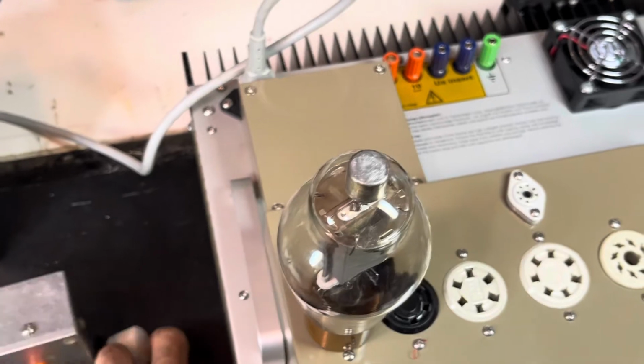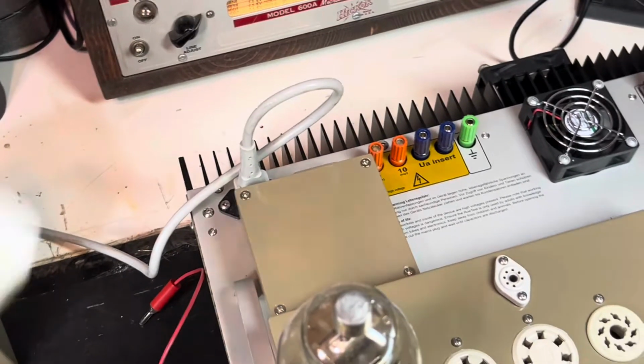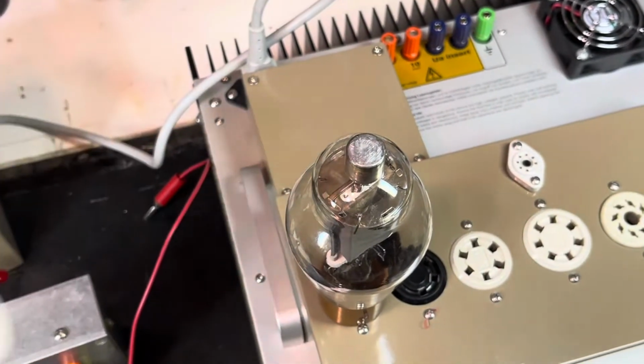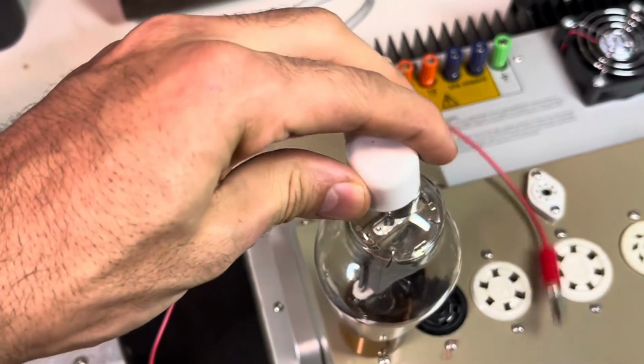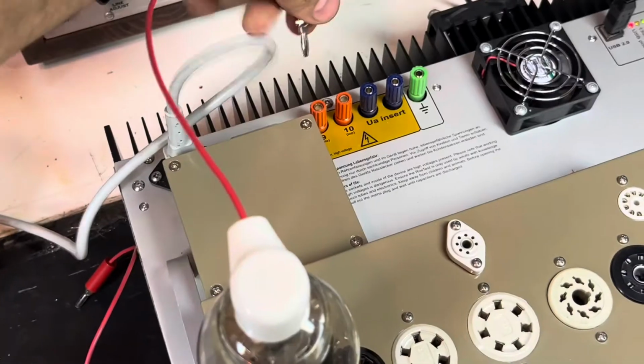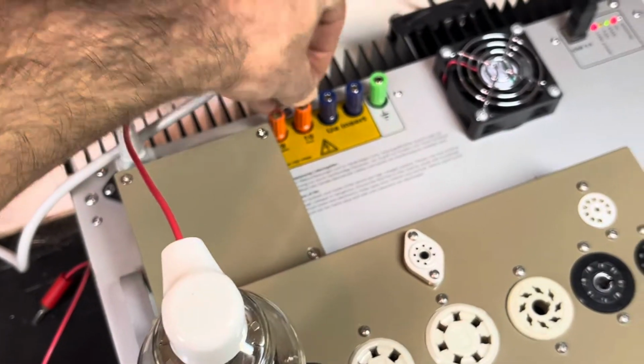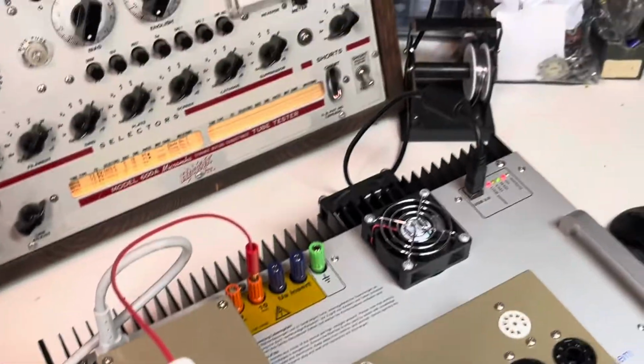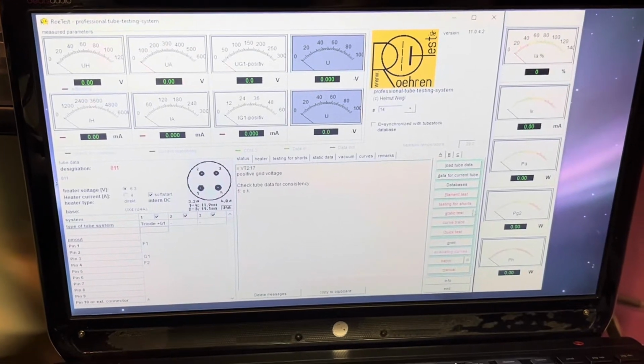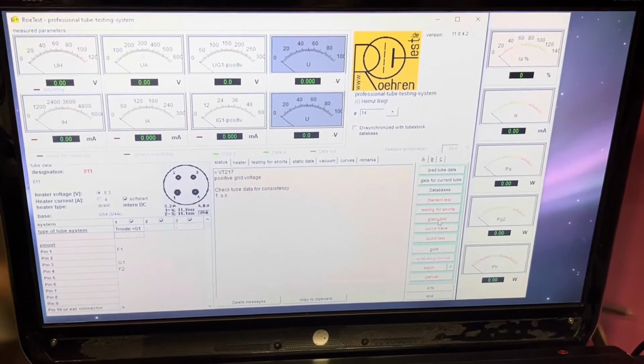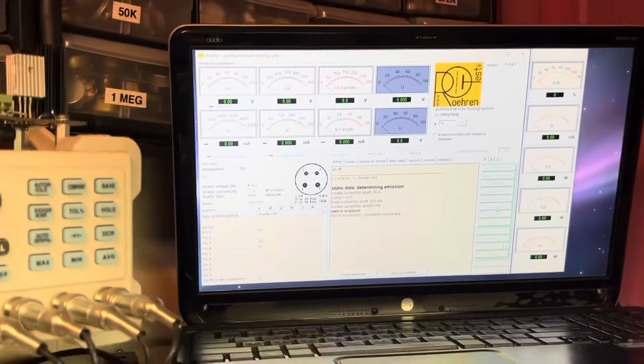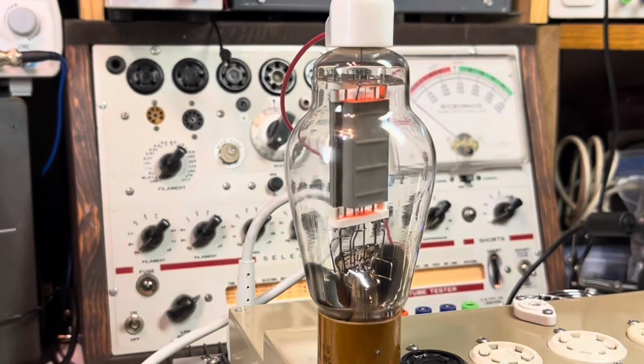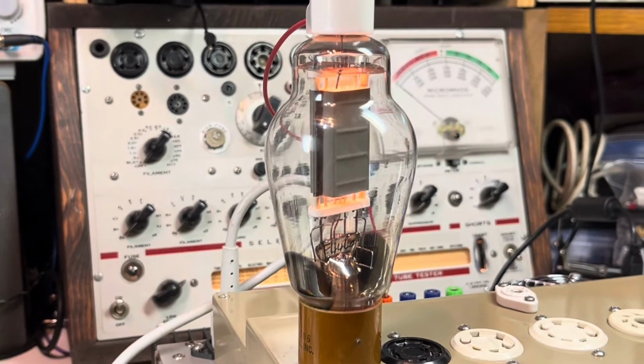When you put the tube on the RoeTest and hit start, the first thing the RoeTest does is a soft start of the filament. So here's the anode cap, and it slowly ramps up the filament voltage. And here's the top. So now we're all connected, so the tube doesn't get a filament jolt. So I'm ready to do a static test. I hit static test. Hear the relay click in, and then the filament soft start, as you can see.